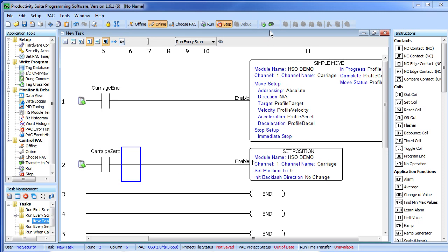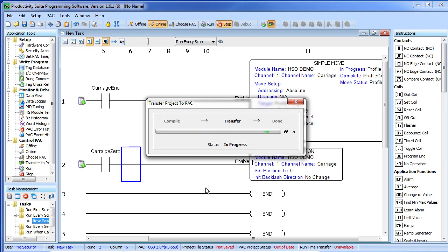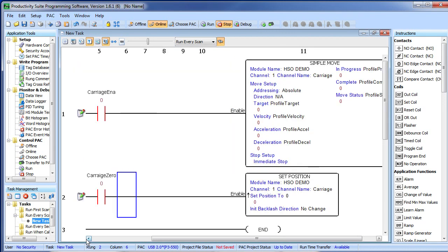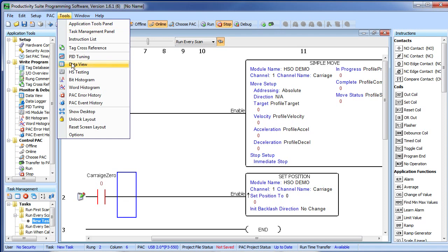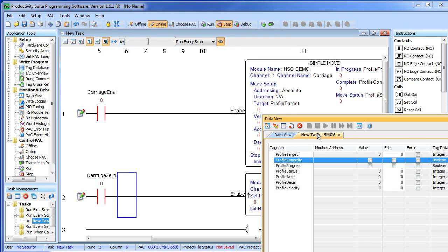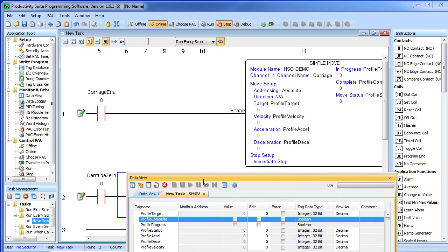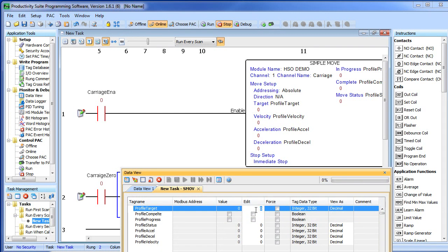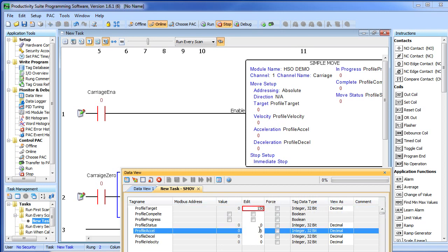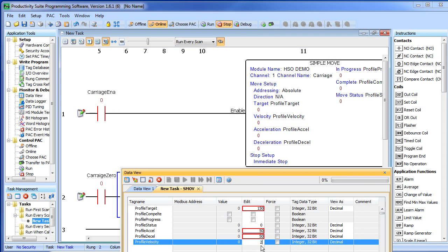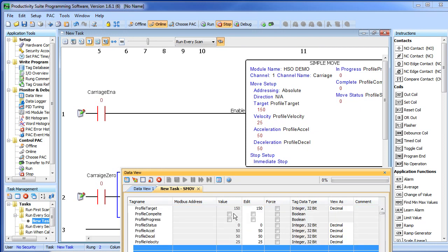Let's transfer this down to our processor, turn on monitoring so we can see what is going on and bring up the data view so we can adjust some of those parameters. There's all those parameters that got preloaded for us. So let's see, we want our target, let's head out, oh I don't know, 150mm. Let's set our acceleration at 50, our deceleration also at 50 and our velocity at 25mm per second. Let's select all those, write them out, verify that the values actually got written into memory and they did and we should be ready to go.